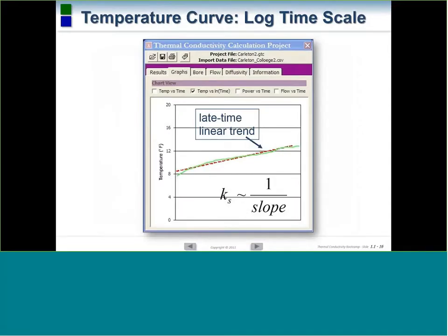Kind of a closer look. This is a zoom in on a very specific time period of the line of best fit in that natural log graph. Just kind of showing you where the line of best fit is versus the actual data. You'll see that there is a little bit of variation that'll happen over the test, whether it be atmospheric effects, but what we're looking at here is very minute changes over time, and it really allows you to zoom in real close and see if your line that the calculation's being done on fits the line of best fit that GLD programs in for you.